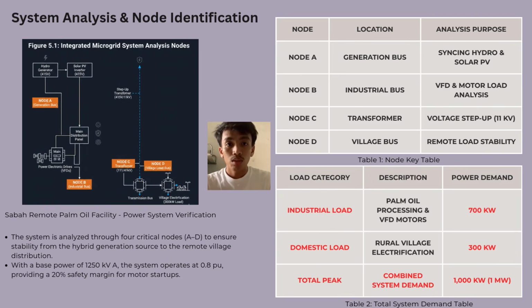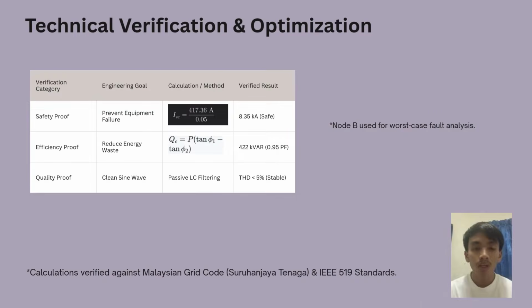Node A is our generation bus where hydro and solar power combine. Node B is the industrial hub powering our heavy VFD controlled motors. Node C and D represent the transmission and the final village distribution. Our total system demand is 1000 kilowatt. We have designed the system at 0.8 per unit PU loading. This 20% safety margin is vital. It ensures that when the large palm oil extraction motors start up, the village at Node D doesn't experience a voltage drop or blackout. Now, let's look at the engineering method that secures the system.